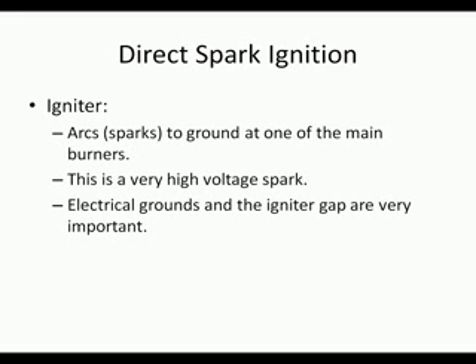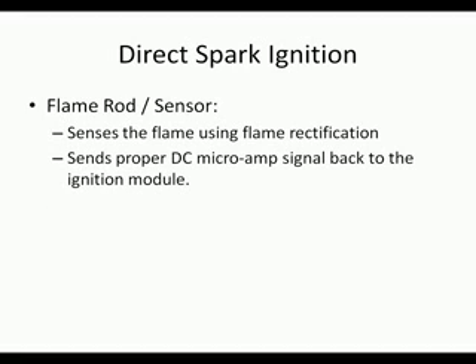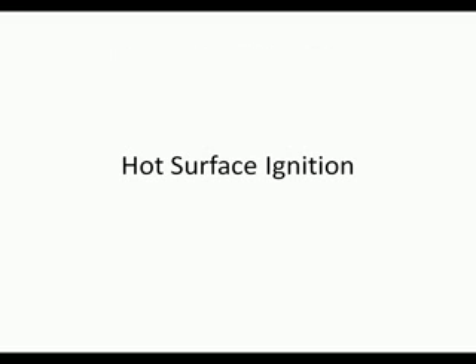These modules use a very low input voltage. It's usually 24 to 26 volts. I use 25 as my middle number. It has connections for the gas valve, igniter, and flame sensor. The igniter arcs the spark to ground at one of the main burners. It has a very high voltage spark. The electrical grounds and the igniter gap are extremely important. The flame rod or sensor senses the flame using flame rectification. It sends the proper DC microamp signal back to the ignition module.